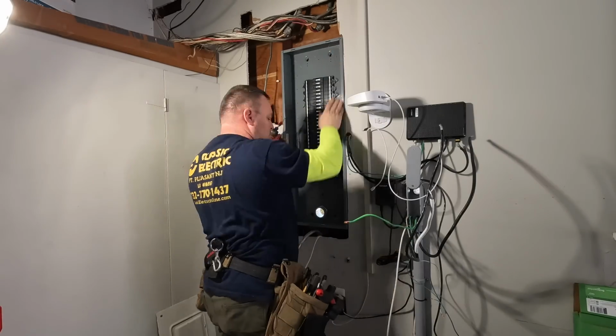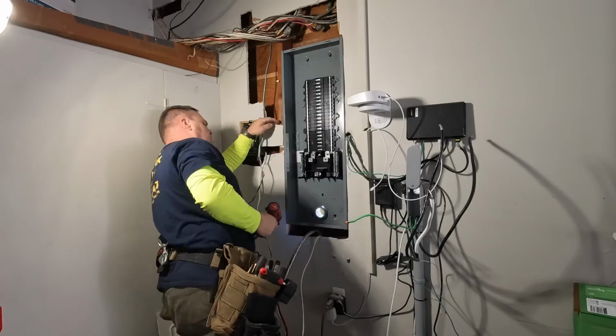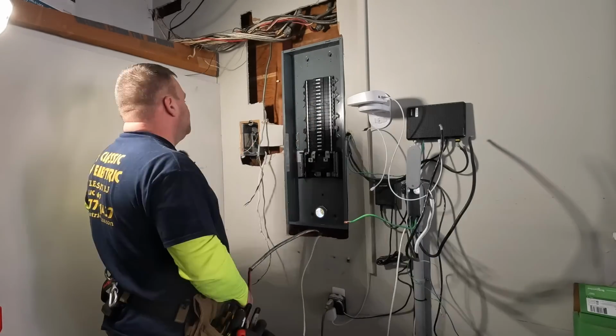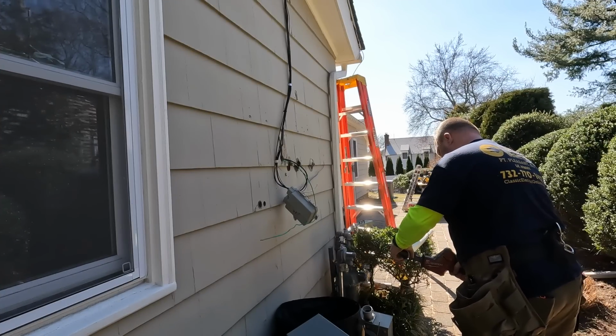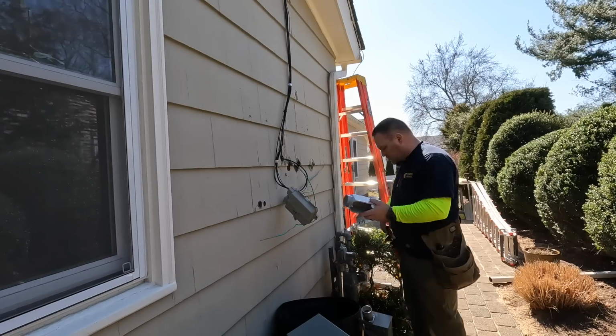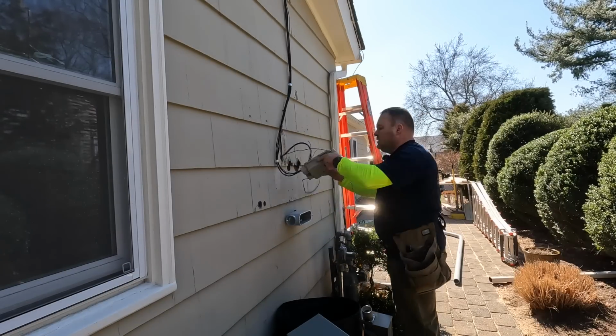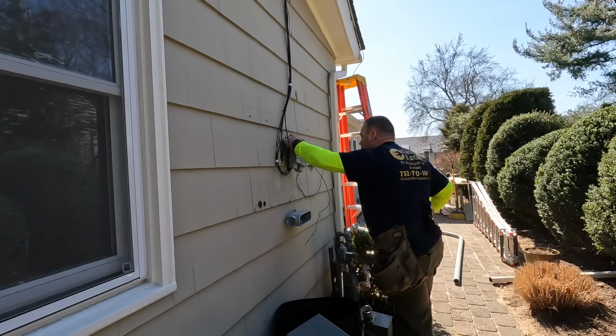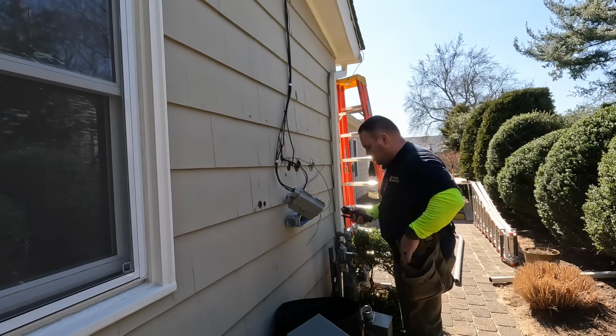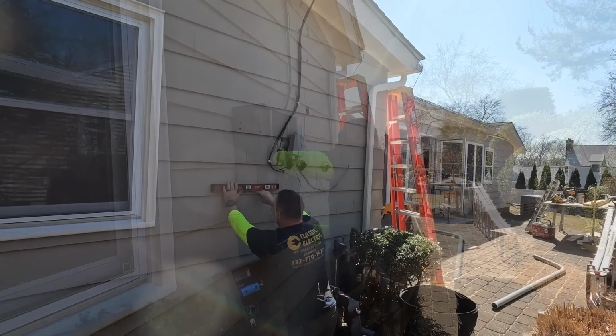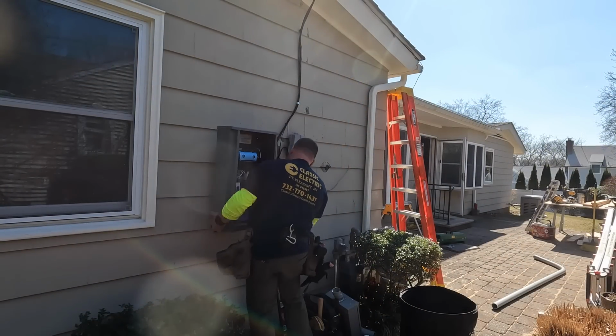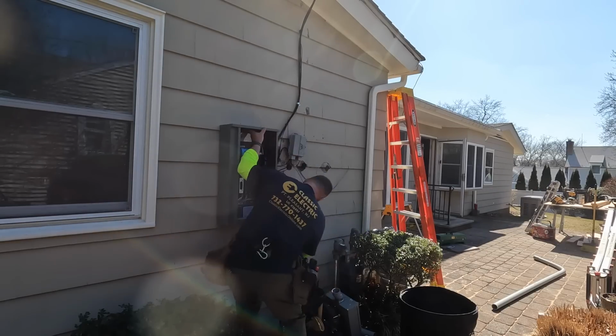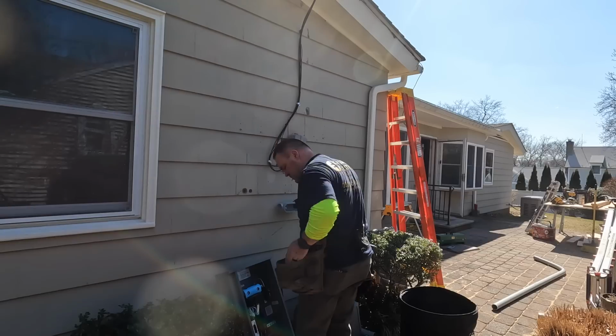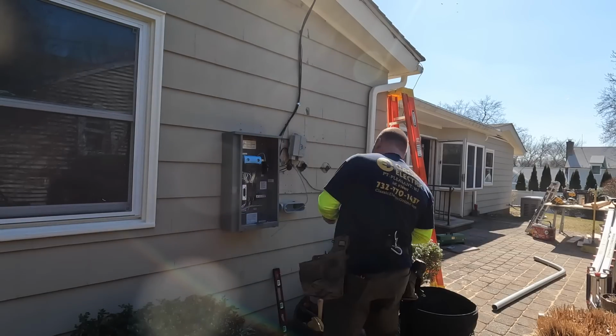So I got the pilot hole drilled and the hole saw drilled, and I'm coming into the bottom of my new panel enclosure here, which is very nice because when you're running your conductors, your feeders from the main disconnect here, which is the automatic transfer switch, it goes right into the bottom of the panel, and then those feeders go right up into the bottom of the lugs. Of course, those lugs you can put on the top or the bottom. I decided to put them on the bottom to leave more gutter space for my branch circuits, so when I go to land my circuit breakers, everything's nice and neat and orderly.